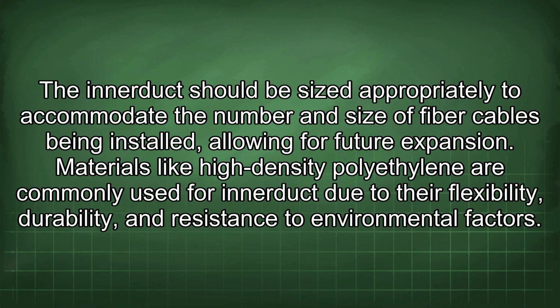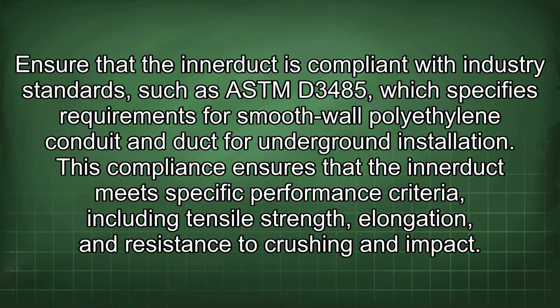The Innerduct should be sized appropriately to accommodate the number and size of fiber cables being installed, allowing for future expansion. Materials like high-density polyethylene are commonly used for Innerduct due to their flexibility, durability, and resistance to environmental factors. Ensure that the Innerduct is compliant with industry standards such as ASTM D3485, which specifies requirements for smooth-wall polyethylene conduits and duct for underground installation. This compliance ensures that the Innerduct meets specific performance criteria, including tensile strength, elongation, and resistance to crushing and impact.